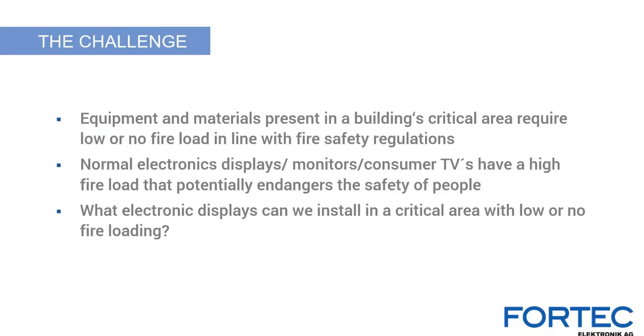The challenge is installing electronic displays in escape routes and other areas where low or no fire load is required. If you want to install visualization in such areas — such as rescue routes — you must comply with the applicable fire safety regulations. It is not allowed to install a normal display or consumer TV in these areas, as they have a high fire load that endangers the safety of people. Therefore, Distex developed the BLO monitor as a solution.